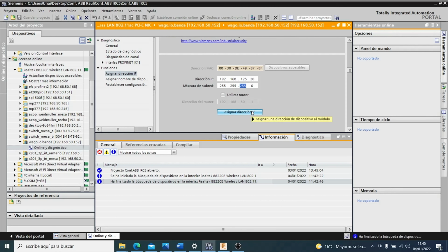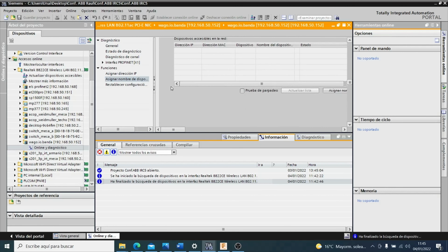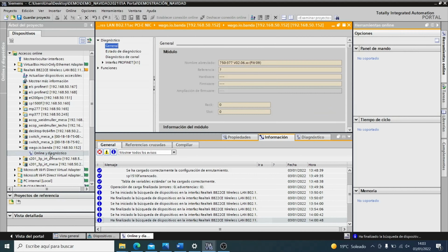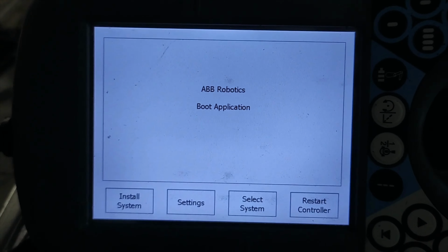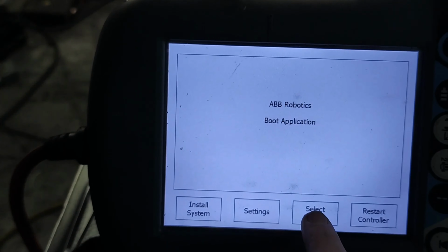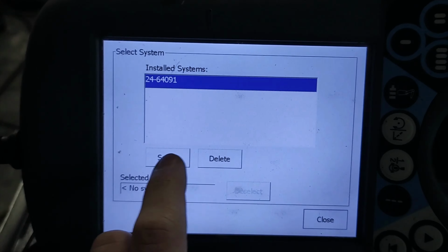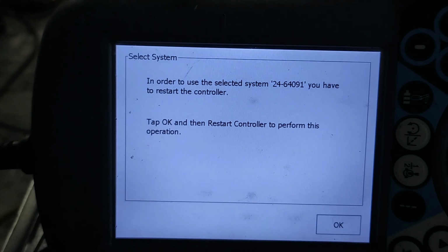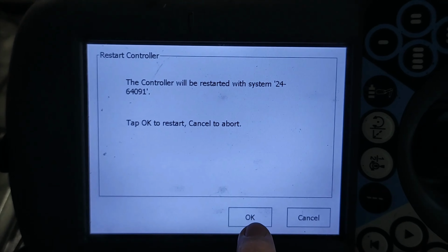Most of these devices, it's very important to double check the firmware, because even if you have the same device, sometimes it cannot connect because of the firmware. In the case of the CP1616, we have verified that different firmwares actually work with each other. So even if you have an old CP1616, like the 00, you can put the firmware 2.4, even though it asks you to put 2.1. And now we will reboot the ABB, and the boot failure LED should stay on green, and the device should also have connected with the controller.